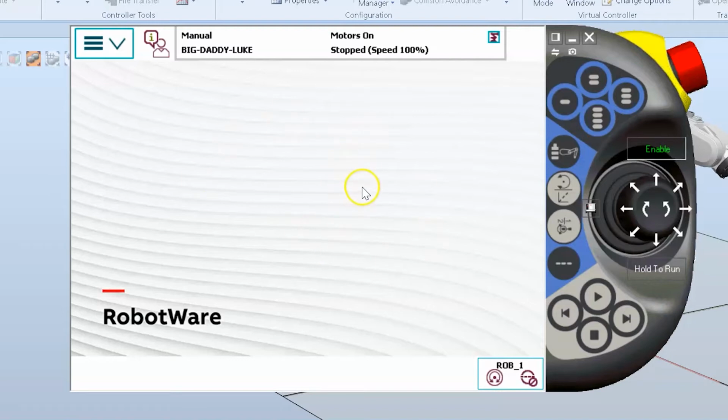And it's always beneficial to read your events, because when there are multiple events, the only ones that are going to show on your screen here are one of two things: either the most recent event or a safety stop like an e-stop. So if I had an issue that led to a failure, I may not see the first events that actually caused it, the things that preceded the actual failure. And that's where our event log will come in handy.